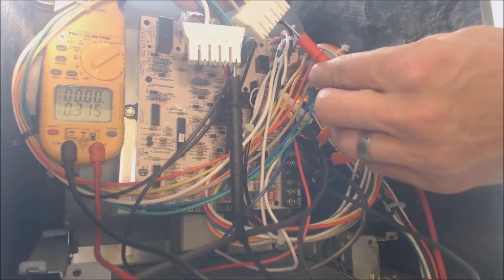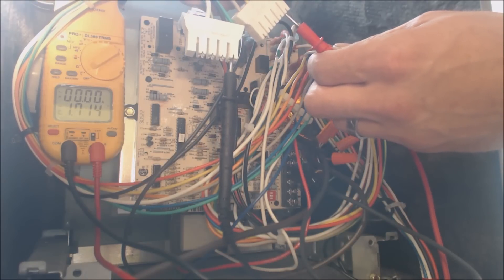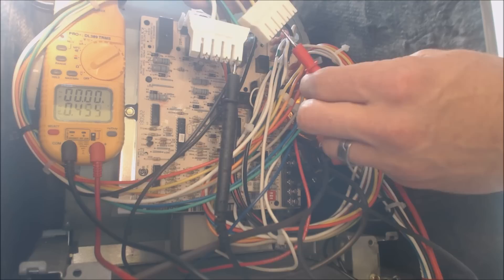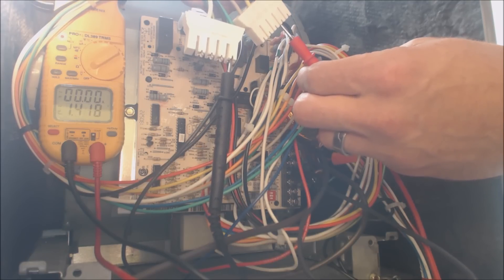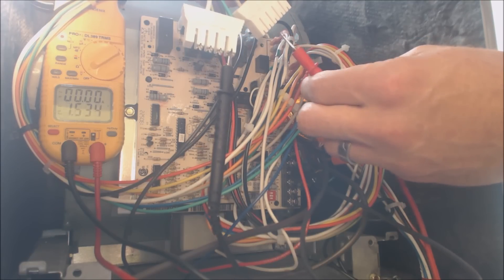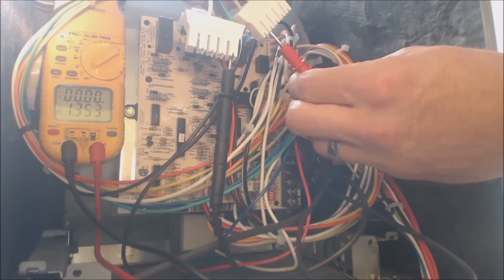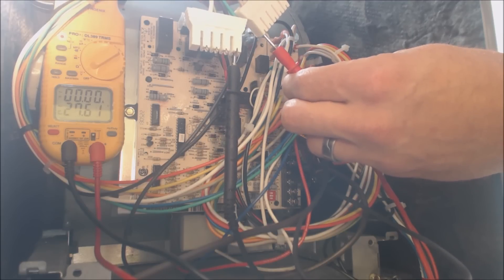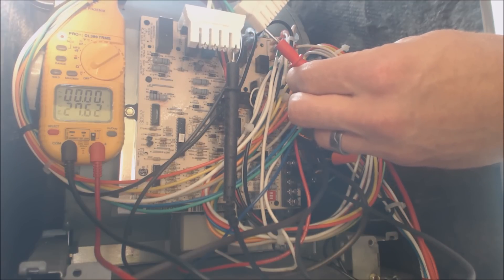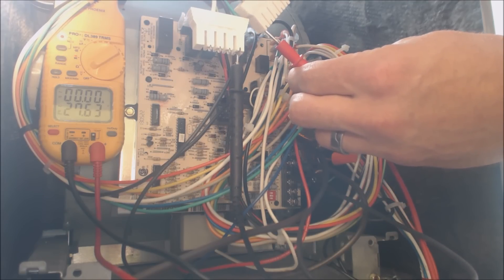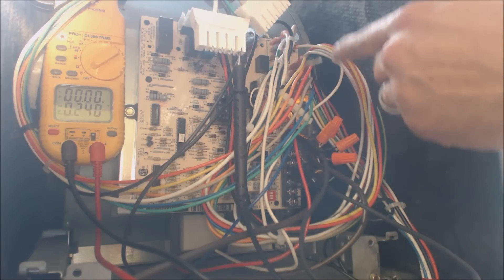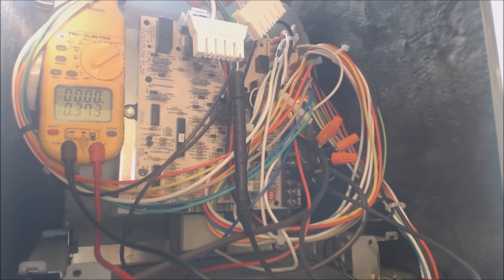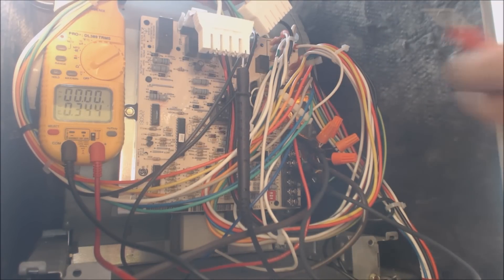So the low speed, which is what it normally sends in a PSC blower motor, it's not sending it with that. Check the orange. It's not that. Blue. Not that. Yellow. Not that. The gray seems to be where it's sending the power to. Okay, the gray on this particular control board is actually the cooling.